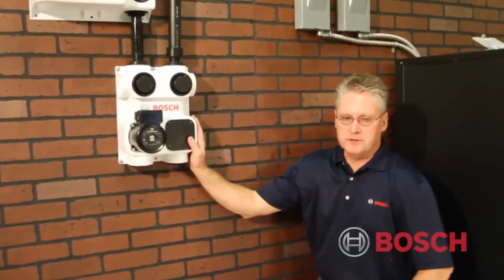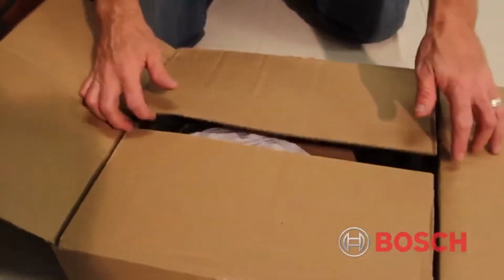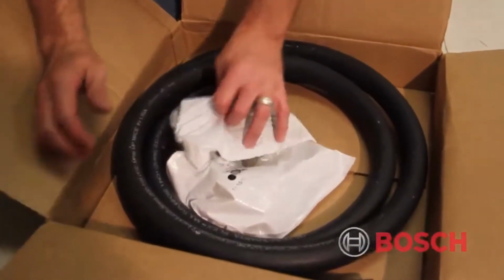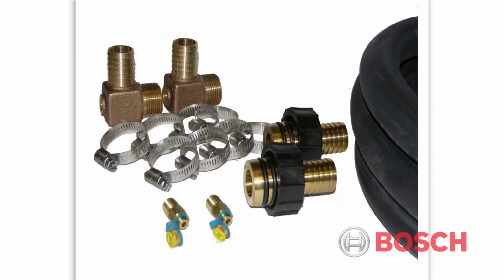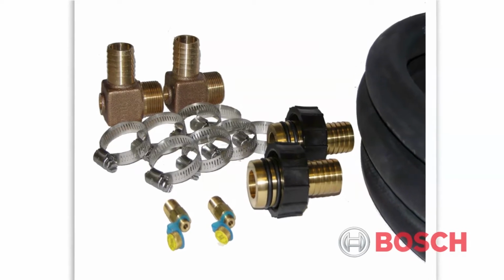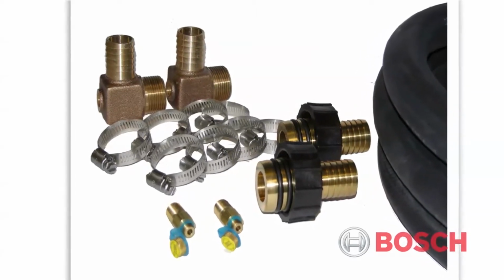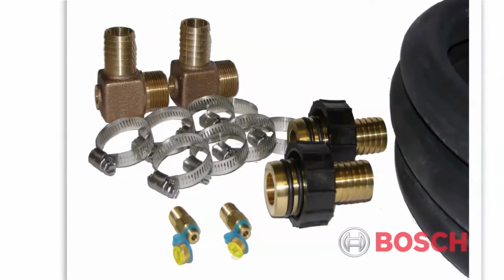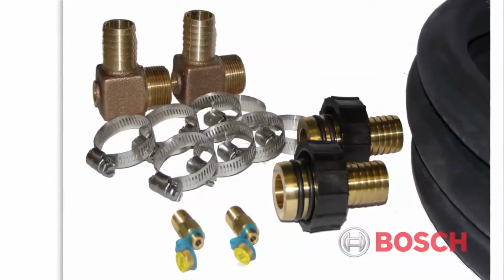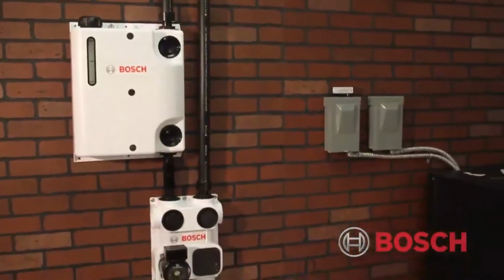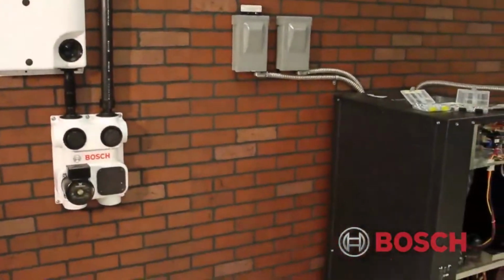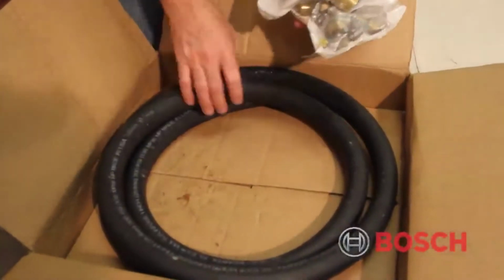We've got the one pump flow center mounted on the wall. And now we're going to take our flow link connection kit and we're going to open it up. This particular kit is a 3/4 inch. The items in the kit are a 10-foot section of 1-inch rubber hose, stainless steel hose clamps, 2 Pete's ports devices, 2 brass 1-inch to barb and 3/4 inch MPT connection elbows. The flow center will normally be set within 5 feet of the equipment. Thus, this 10-foot rubber hose inside the box will be cut in half.